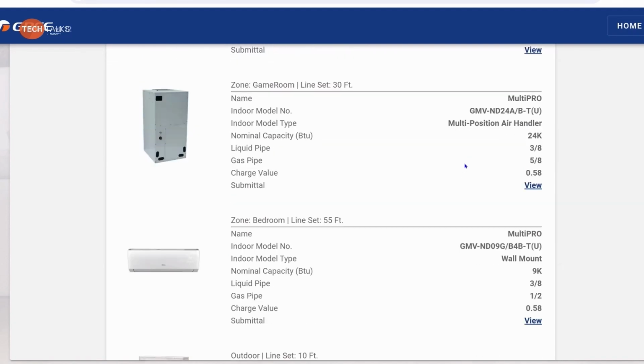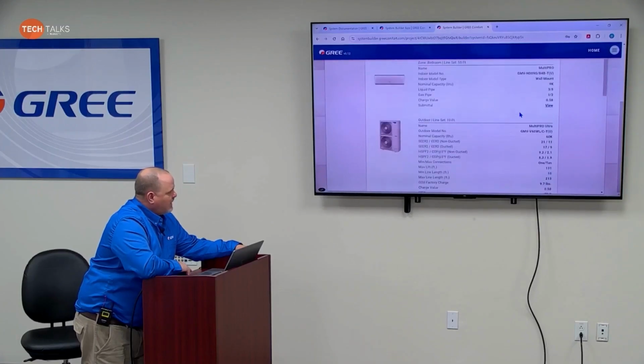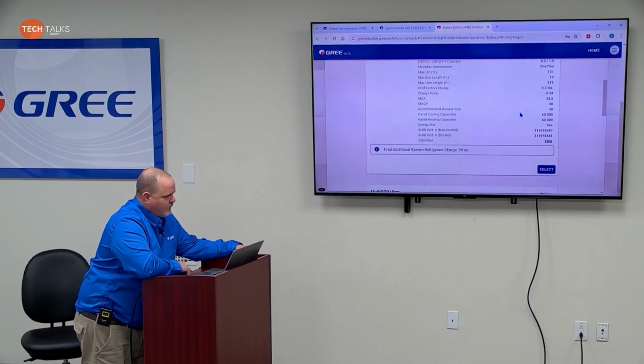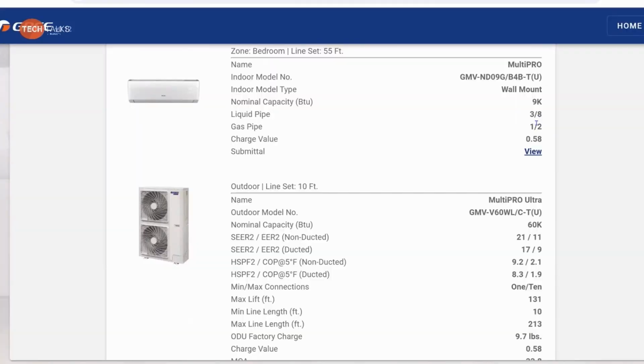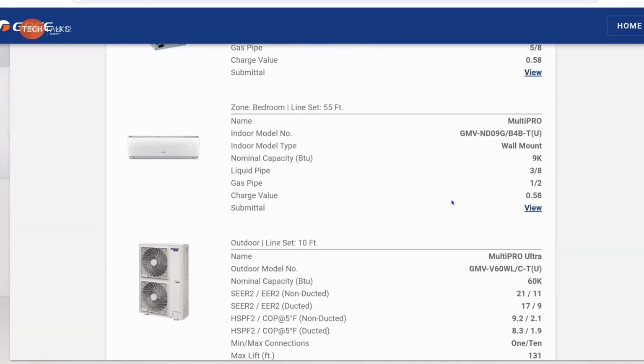The point I'm getting at, and you're going to learn as I go through the PowerPoint, the basic layout rules that we have restrict you to 49 feet or less, or even just call it 50 feet. A foot's not going to make or break you. When you breach that 50 foot, it's going to increase the pipe size, which is not a problem. As long as we increase the pipe size, that's not an issue. What becomes an issue is if you do that from that header to that indoor unit, you're going to have 3/8 half inch pipe. Once you get to the indoor unit, you got to reduce back down from 3/8 to 1/4 and from half inch to 3/8 to be able to connect it to the flare on the indoor unit.